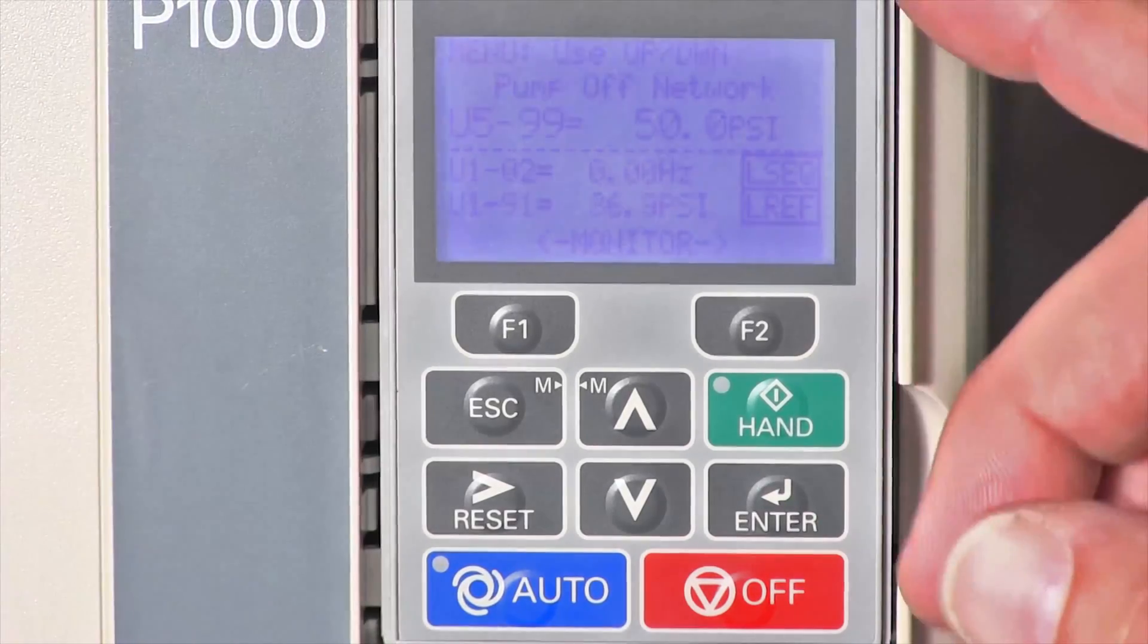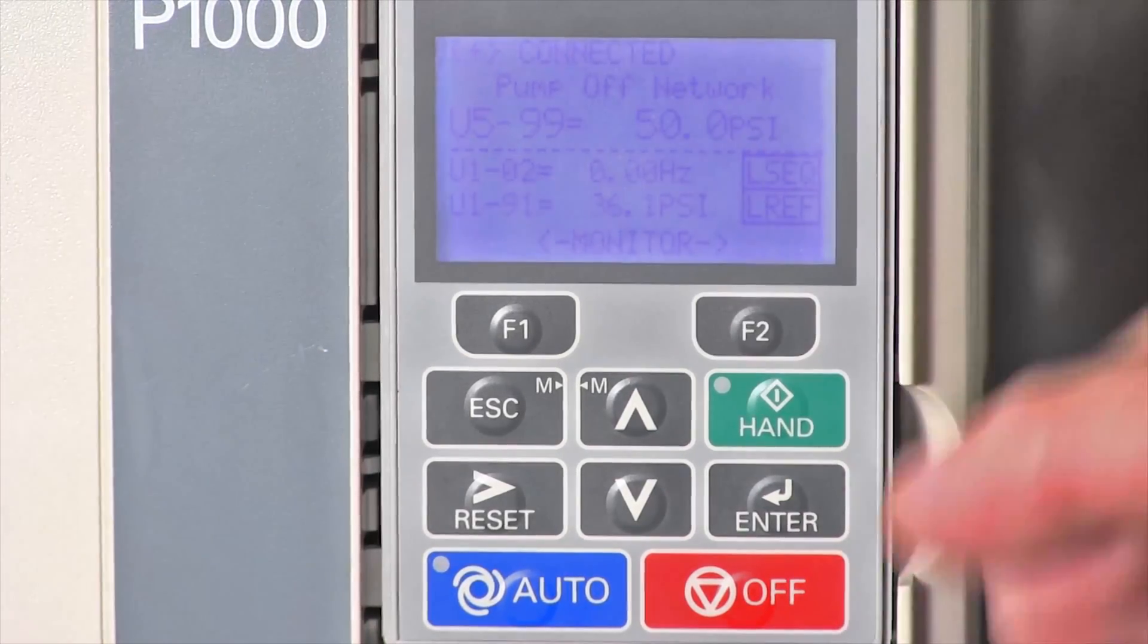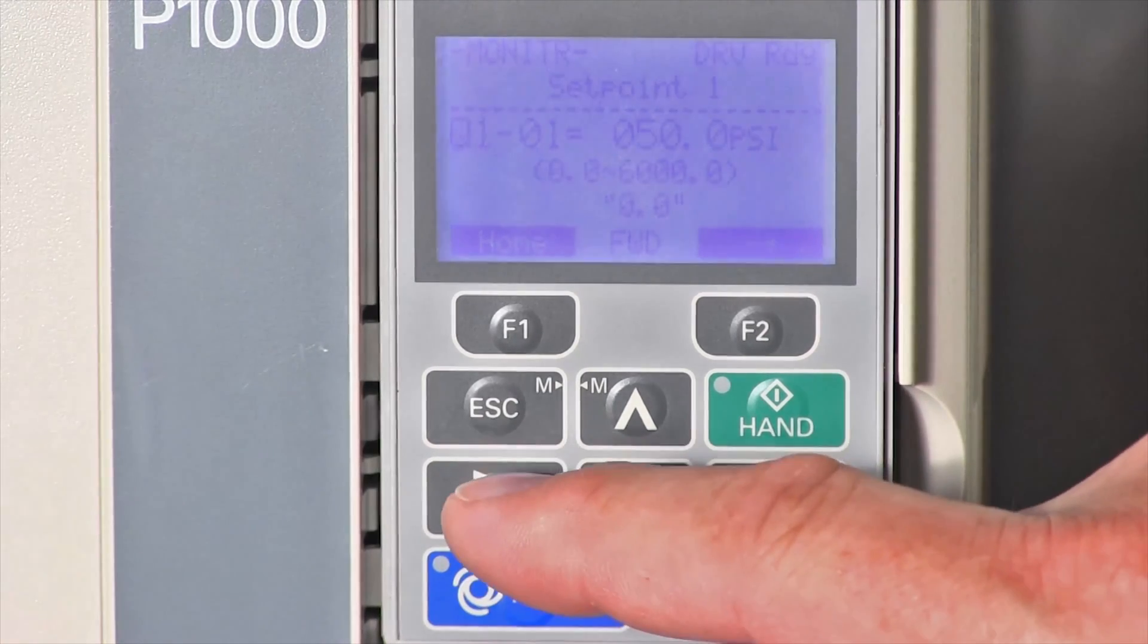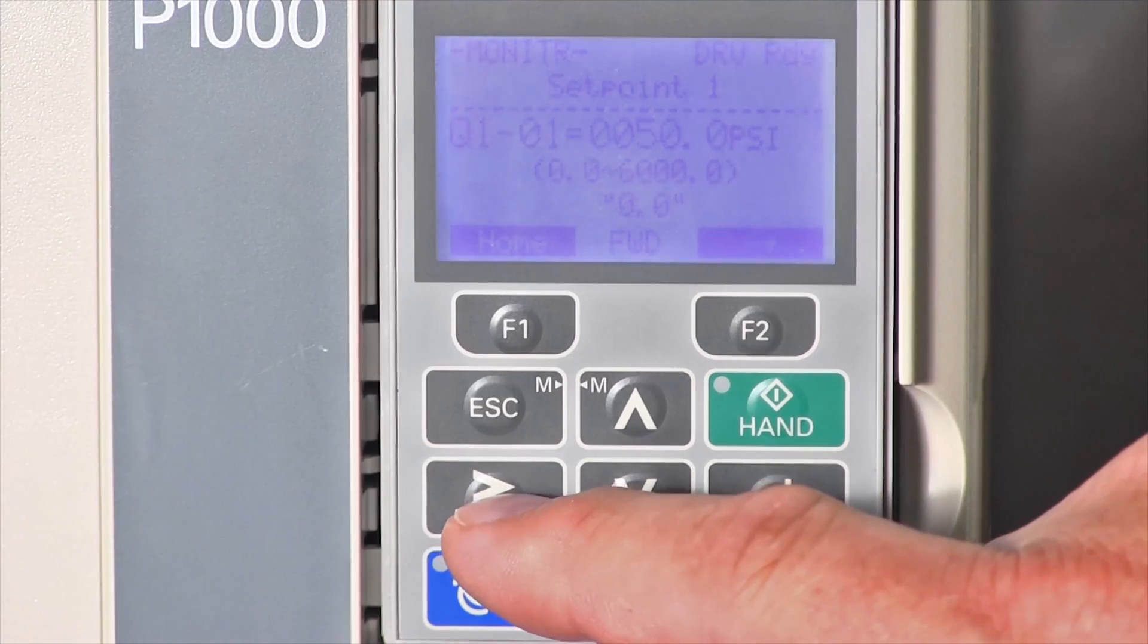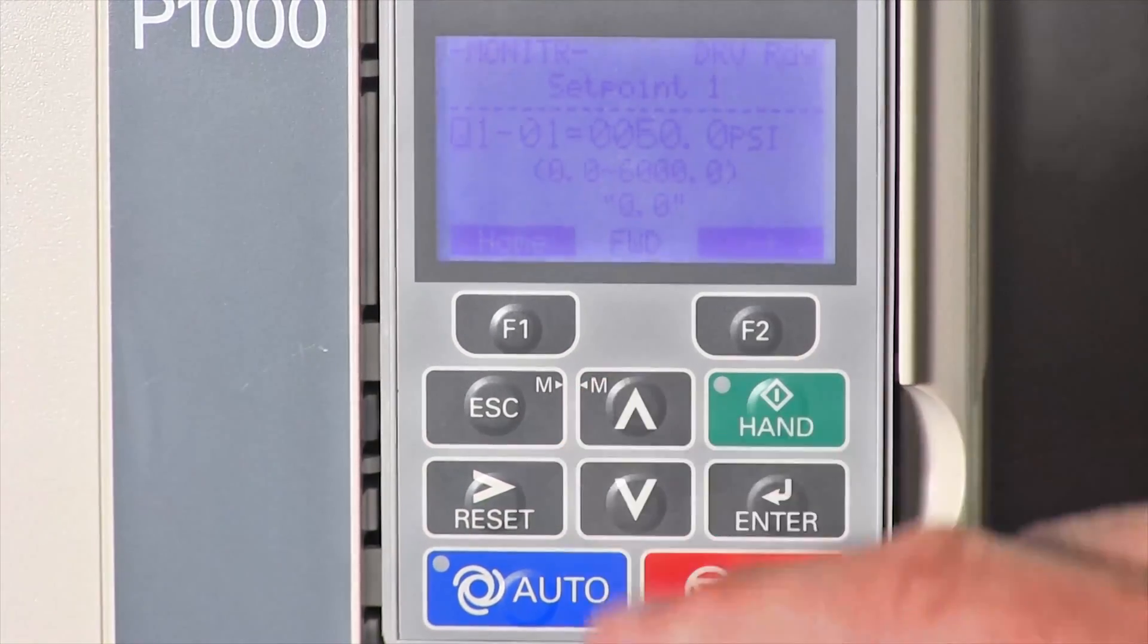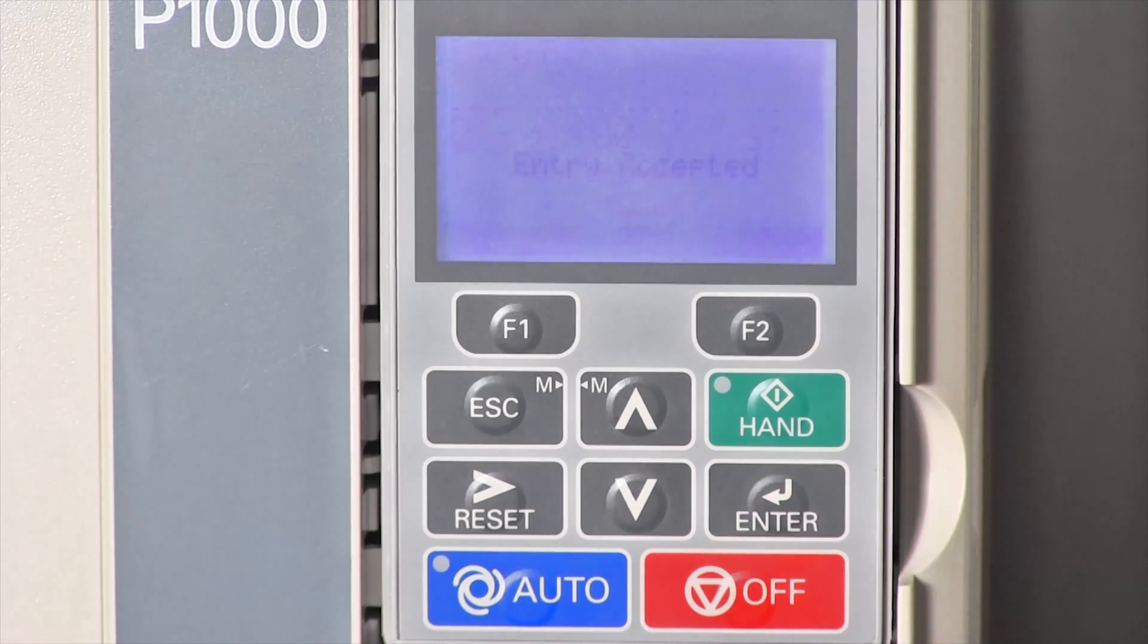The boosters arrive with a set point at 50 PSI. To change this, simply press enter, use the arrow over button, move to the tens column, or in this case to 5 and 50, and then use the arrow up or down to change. In this case, we want to change it to 60, and then when we're done, we'll press enter.